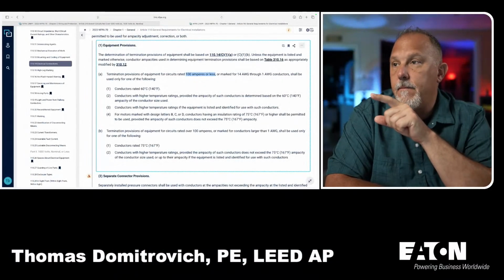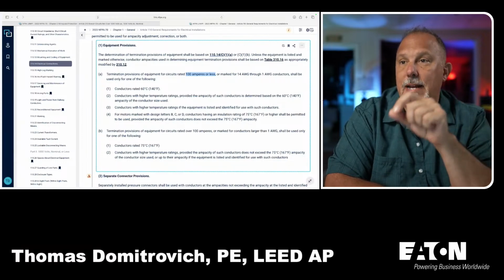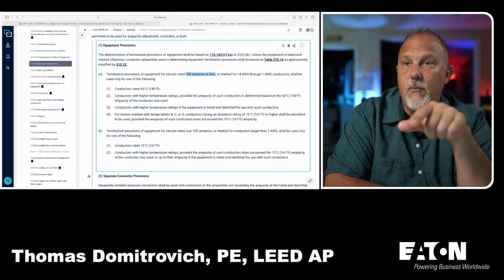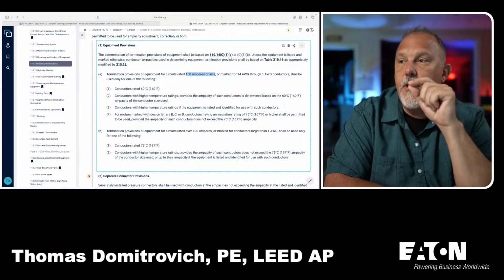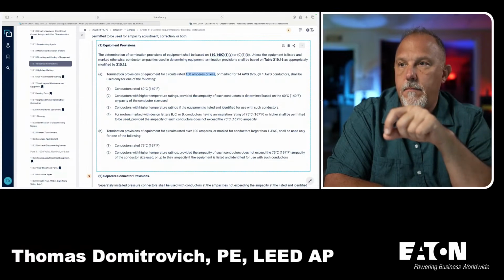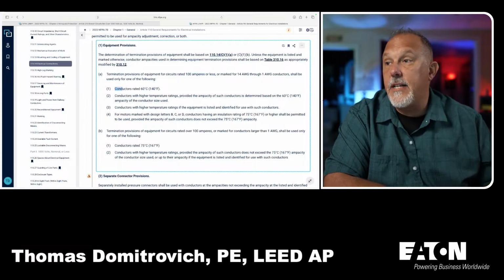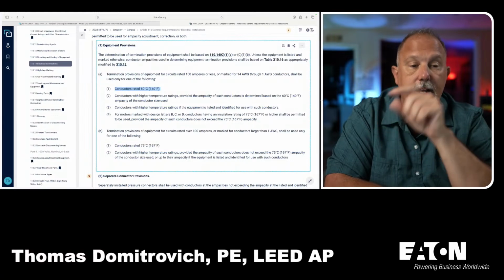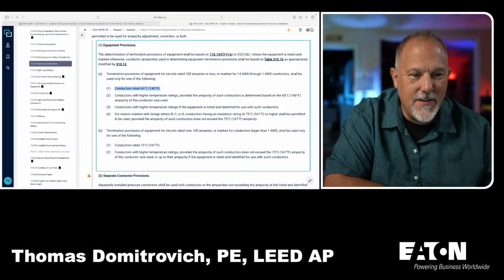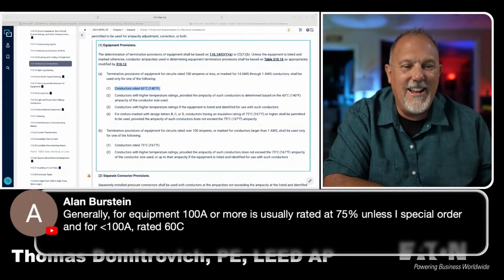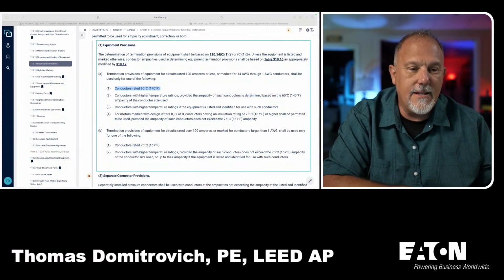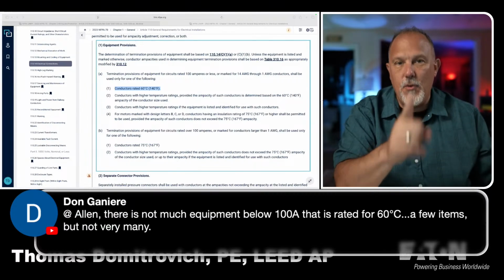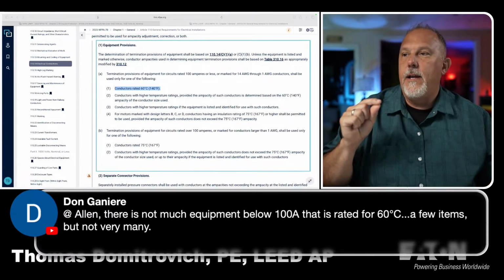What this is saying is termination provisions of equipment for circuits rated 100 amps or less, or marked for 14 AWG through 1 AWG conductors, shall be used only for one of the following. Conductors rated 60 C. Now, Alan, you mentioned this, right? You said 60 C. Generally, equipment over 100 amps is usually rated at 75 unless I special order. Alan, there is not much equipment below 100 amps that is rated for 60 degrees C, a few items. Here it says the default is conductors rated 60 degrees C.